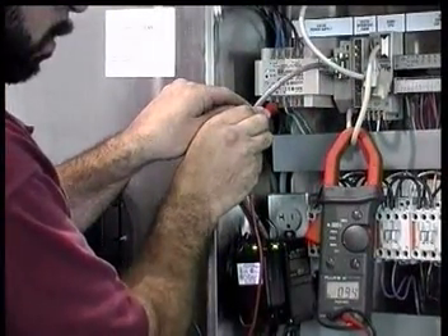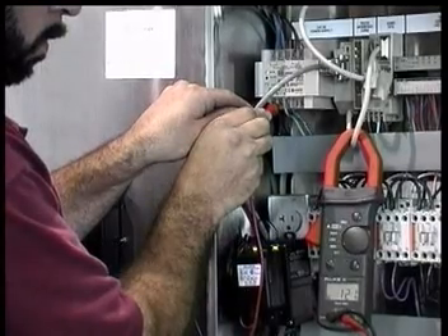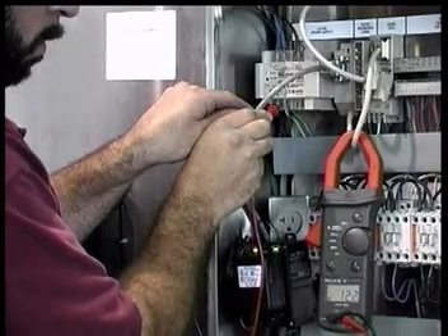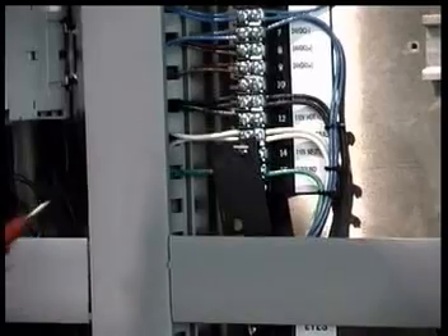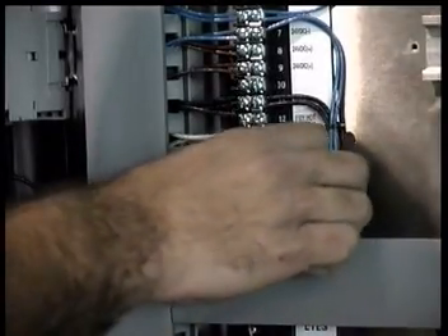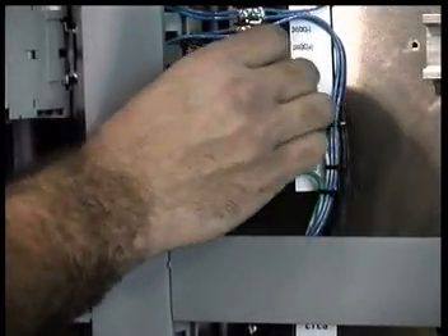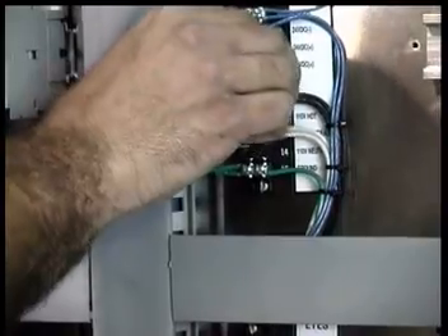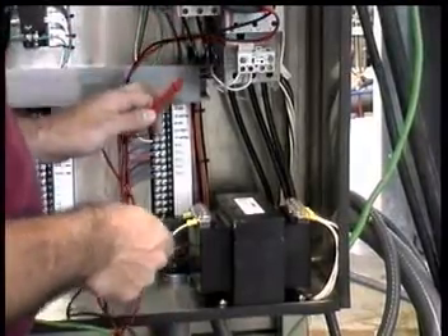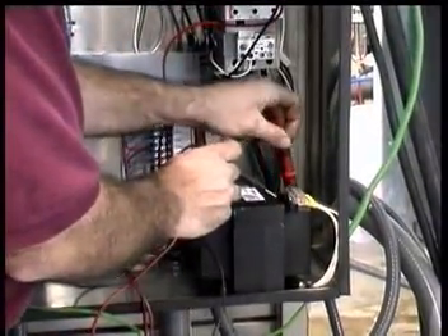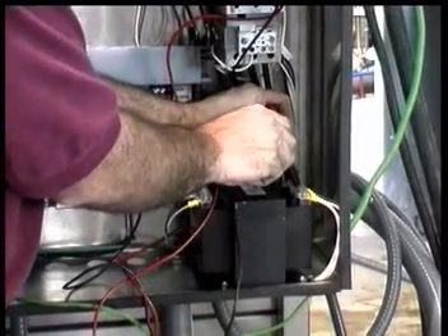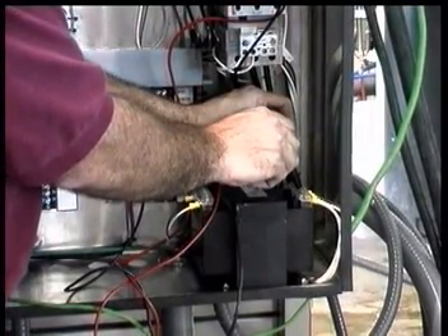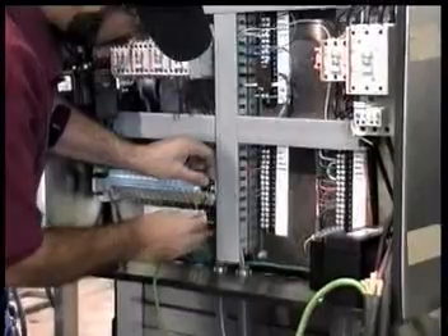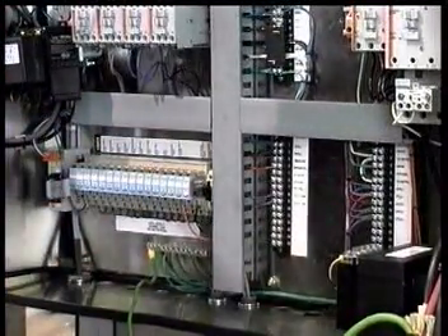Then check for power between terminals L and N on the 24 volt power supply and on terminal strip number 1 between the 110 hot and 110 neutral. Be sure to replace the protective cover. Your final check is at the transformer between H1 and H2. 110 volt power should be present at all locations. Check the 110 fuse on the ZOC16 relay card.